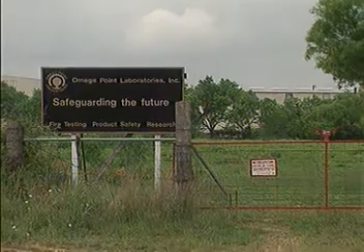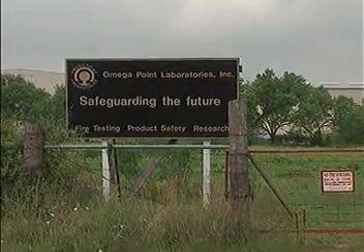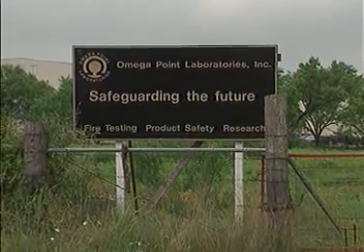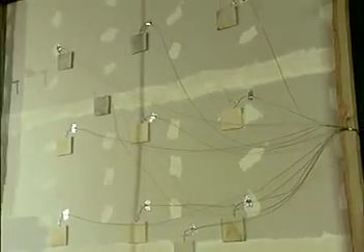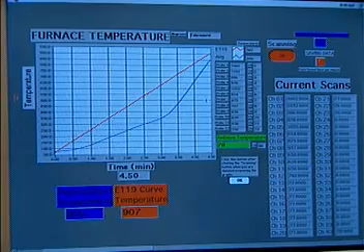It's just a question of how hot they have to be before they catch on fire. A laboratory test is used to determine durability under fire conditions. This test is the official ASTM E119 test, which measures how fast heat will transmit through a wall to set something aflame on the other side.